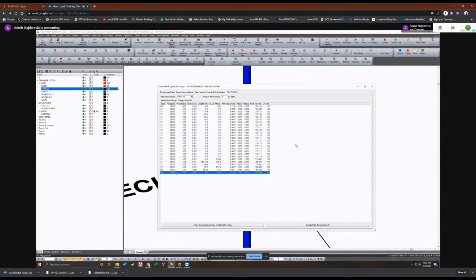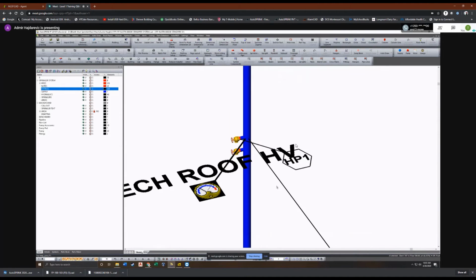The program has the ability to eliminate certain pipe segments. You can zero out the hydraulic length of pipe segments. As far as the equivalent fitting, that 12-foot equivalent fitting is the program accounting for the pipe outlet, the equivalent length value of a T on that standpipe. I don't know if we'll be able to eliminate that. Yeah, that'd be pretty tricky. I don't think you can even select it. Yeah, we might be able to. It might be an option.